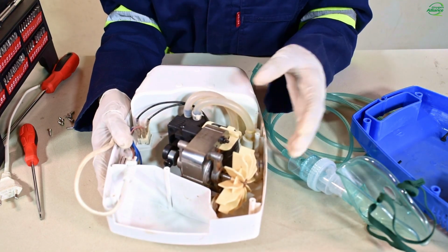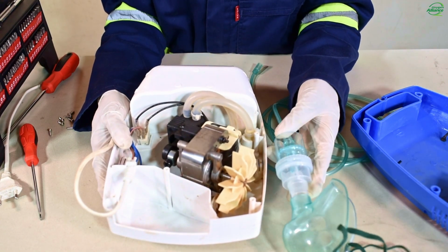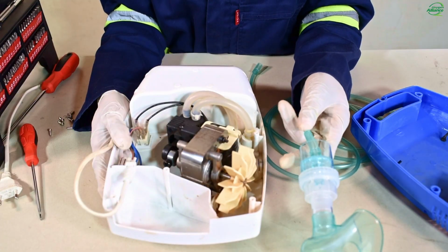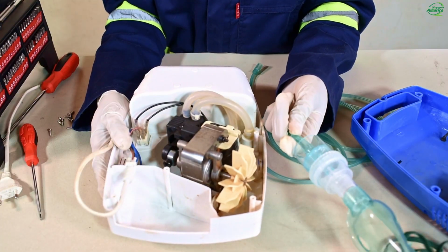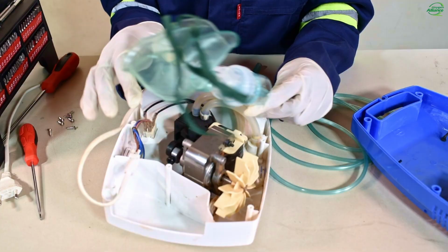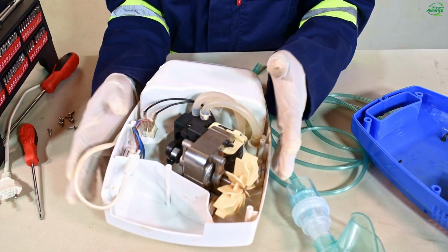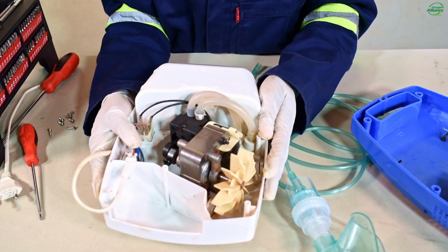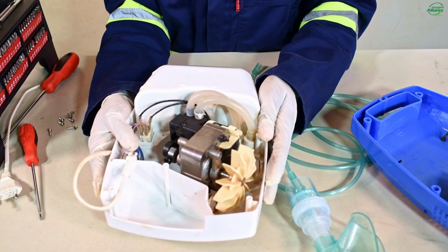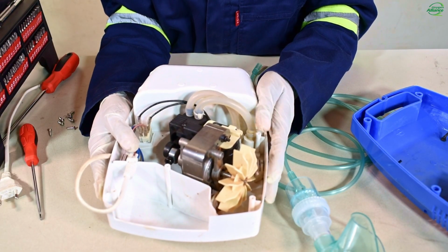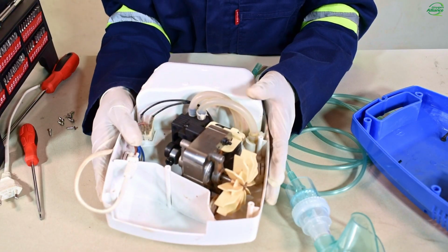Another cause of these leakages include cracked tubings, and these cracks may occur anywhere along the tubings. Make sure that you carefully inspect all connections, and a simple method of doing this is applying foam to the suspected areas while the system is running.